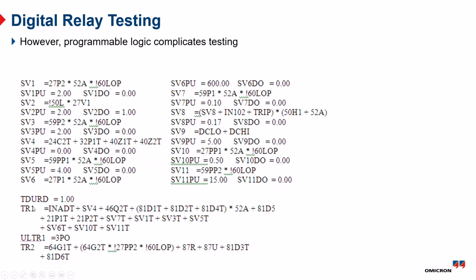So here, for those of you that don't know, this is a trip equation. So any of these relay word bits, what we call the individual elements within a relay, assert, then that would assert this trip equation, and the trip equation is mapped to a physical output. So output, say 101, has TR1 in it. So basically, whenever we get the negative sequence time overcurrent element here, the 46Q2T, when that asserts, TR1 goes to 1, and then when TR1 goes to 1, it's going to fire the output, right? So this is basically the way this works.